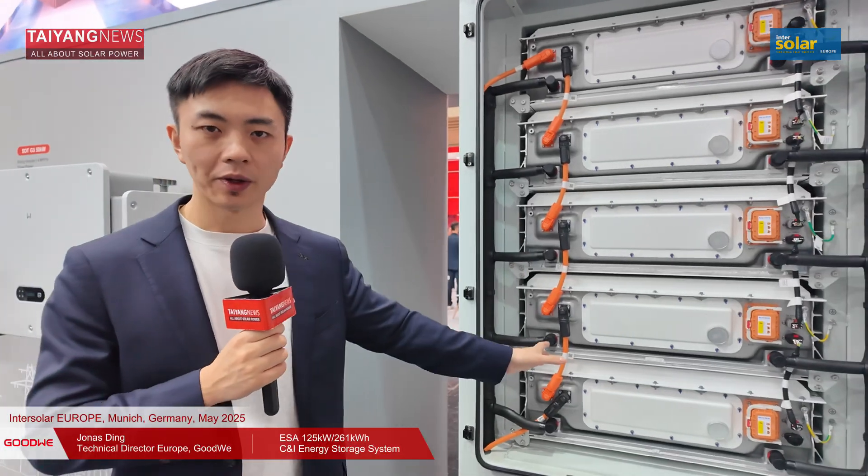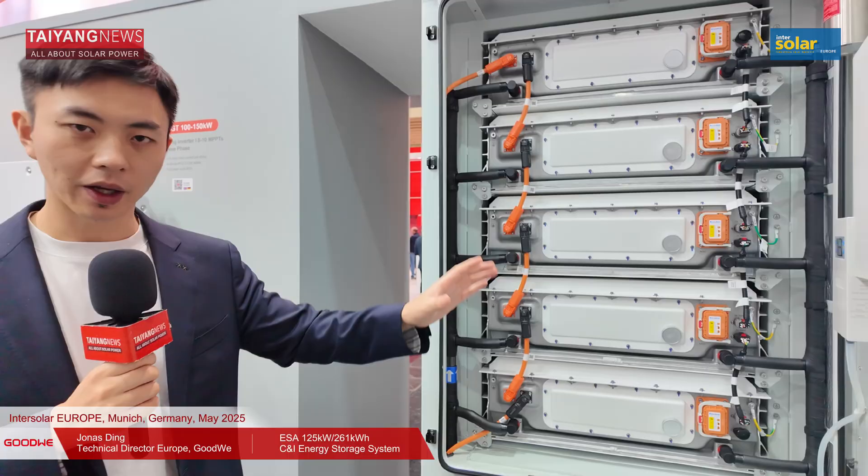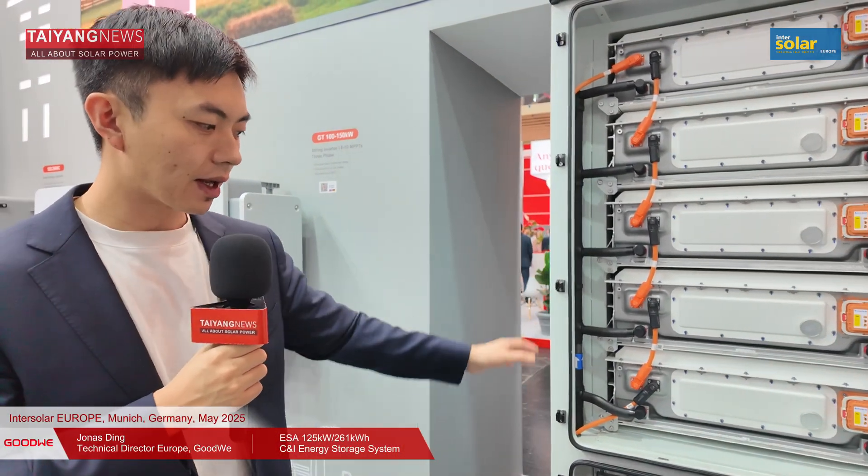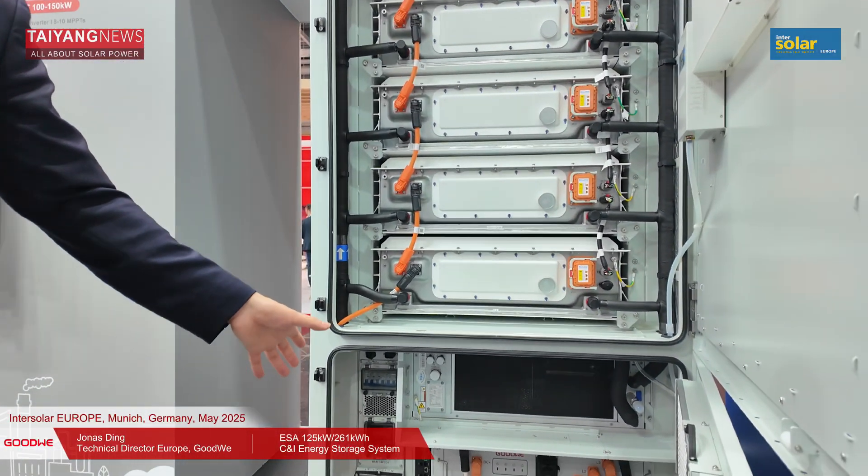Safety is of course the most important thing for the whole C&I solution as well. We protect it with six layers of protection, from the cell level using top-brand cells, to the structural level, and the emergency level. At the emergency level, the system features an aerosol-based fire extinguishing function at the battery pack and cabinet level, as well as a water-based fire suppression function. The cooling system uses liquid cooling for the battery and fan cooling for the PCS at the bottom of the cabinet.